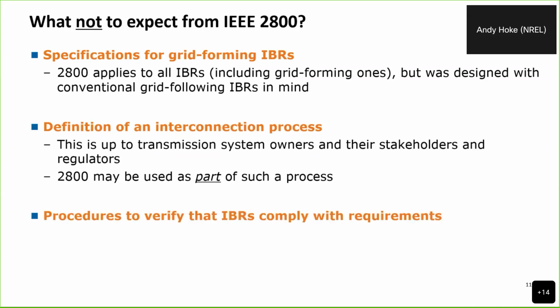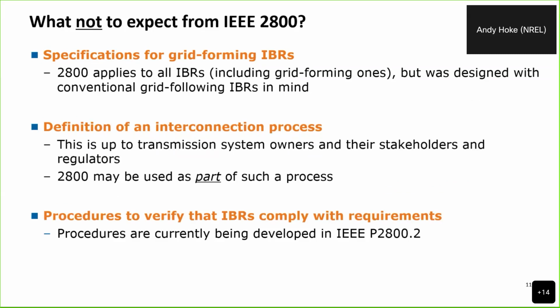I mentioned earlier, it doesn't necessarily provide the procedures to verify that an inverter-based resource complies with its requirements. Those are currently being developed. And on behalf of the 2800 leadership team and the 2800.2 leadership team, it's important to note that we don't see the development of the 2800.2 verification procedures as a necessary step to start applying IEEE 2800. IEEE 2800 could be applied as soon as an entity is ready based on existing verification methods that are already being used in industry.